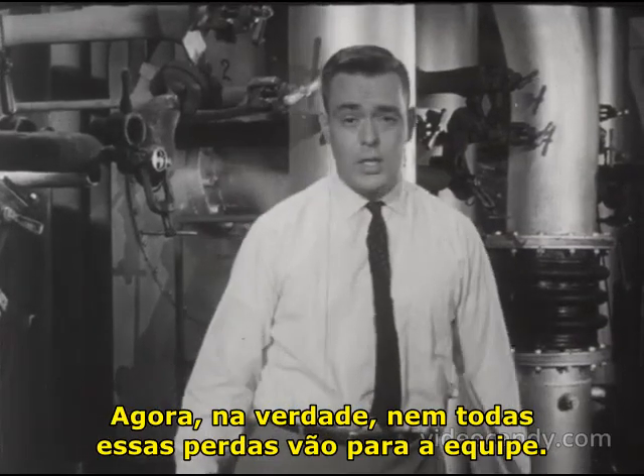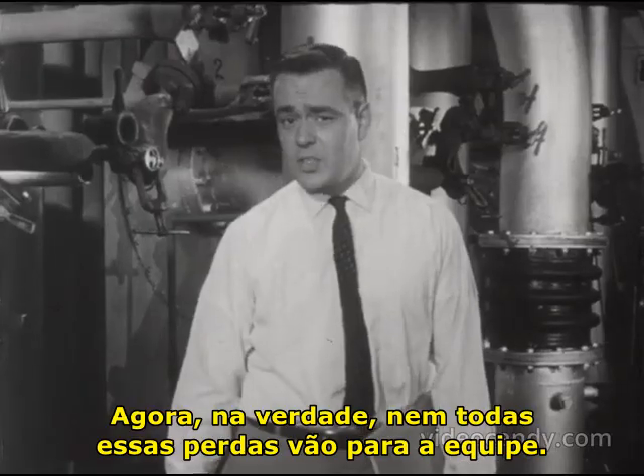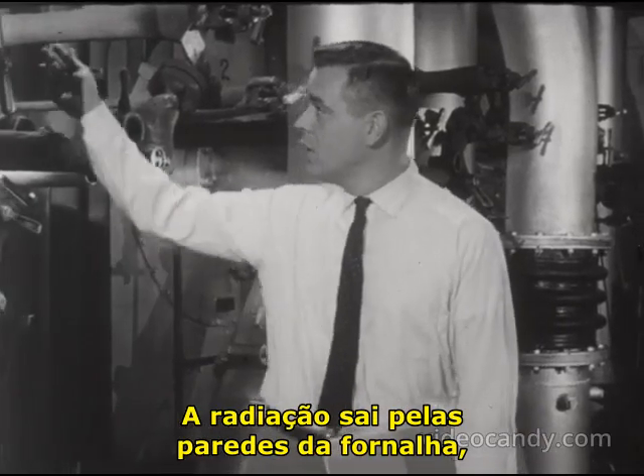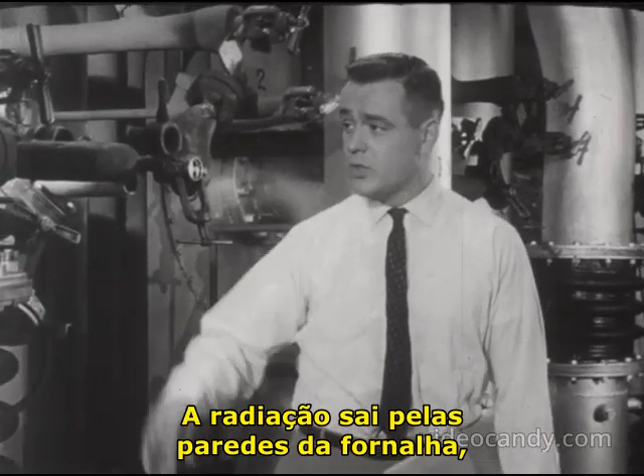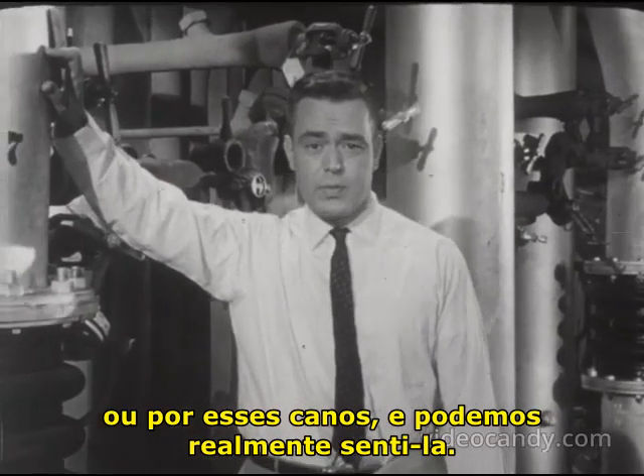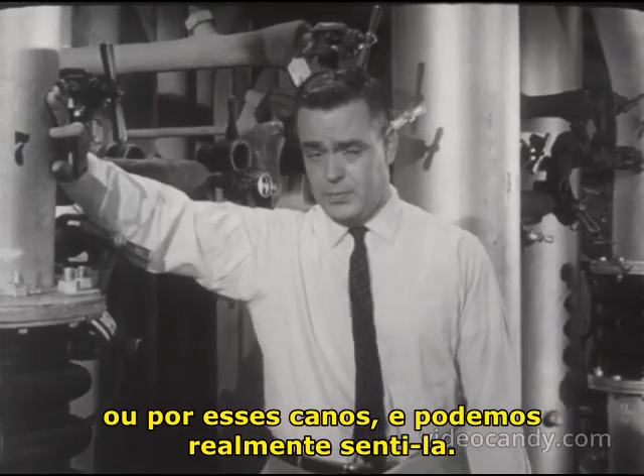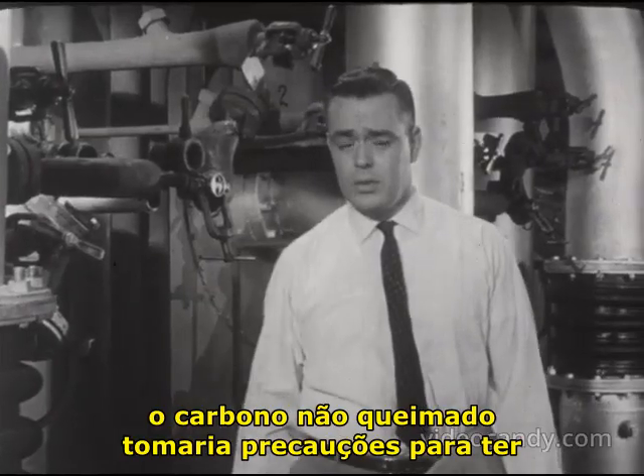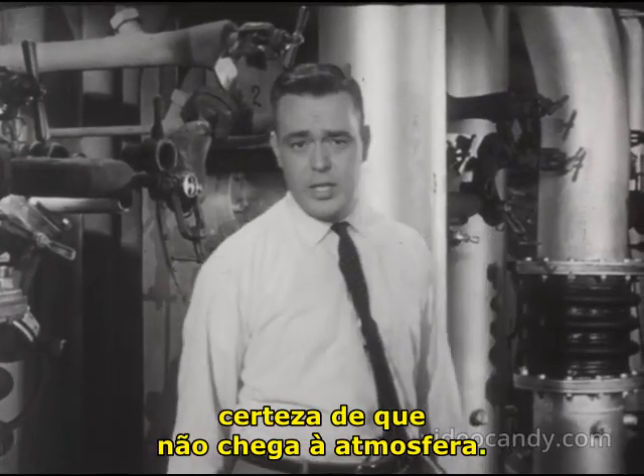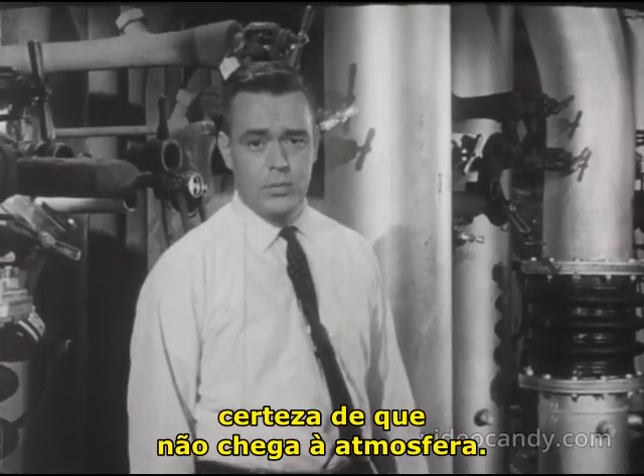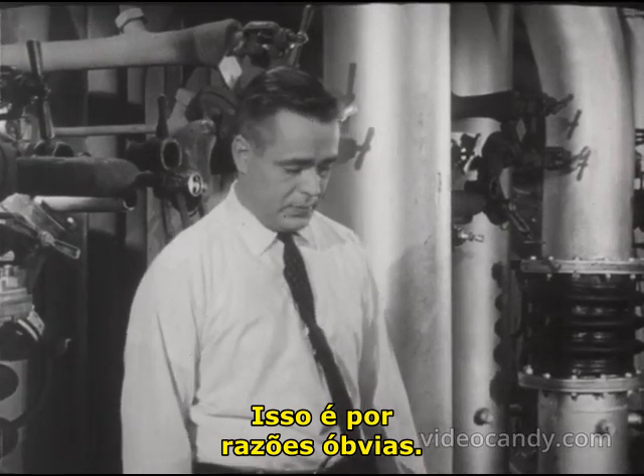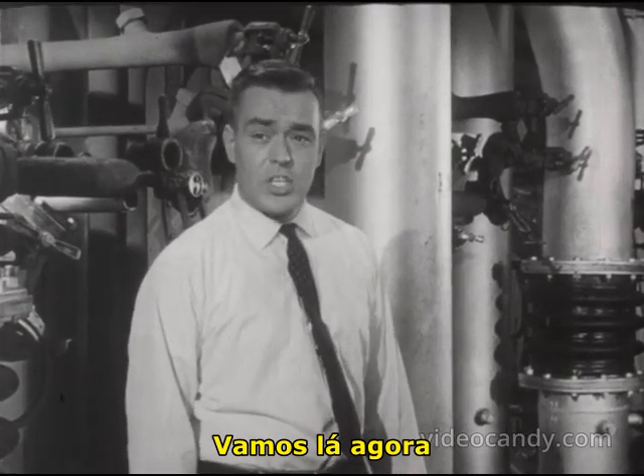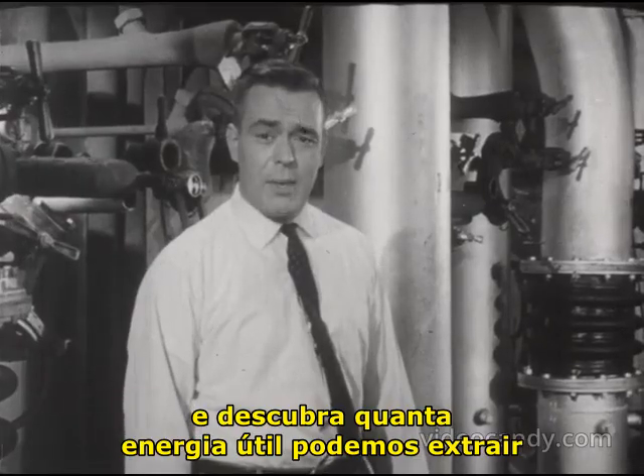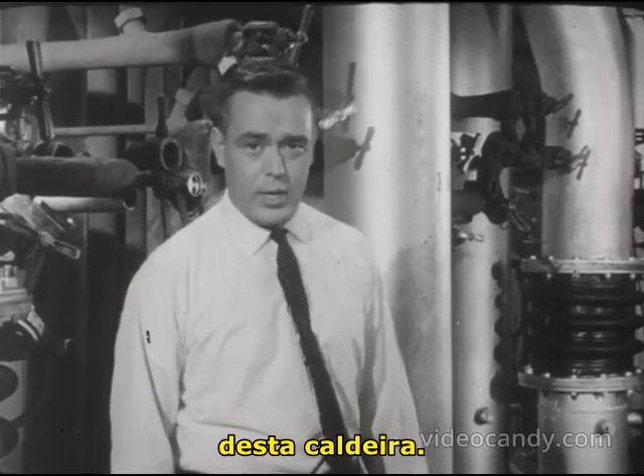Now actually, not all of these losses go out the stack. The radiation comes out through the walls of the furnace or through these pipes, and we can actually feel it. The unburned carbon, we take precautions to be sure that it doesn't get to the atmosphere. This is for obvious reasons. Let's go now and find out how much useful energy we can get out of this boiler.